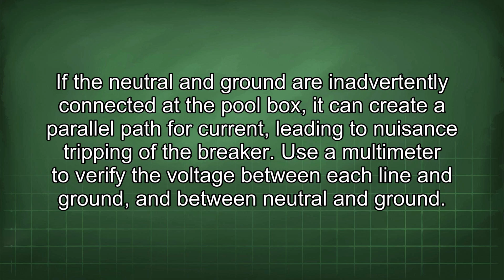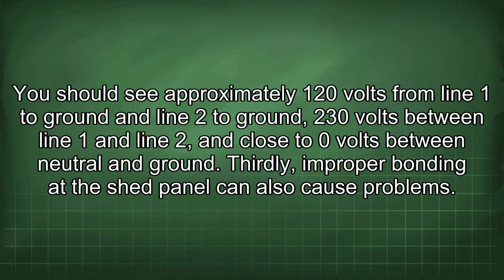Use a multimeter to verify the voltage between each line and ground, and between neutral and ground. You should see approximately 120 volts from line 1 to ground and line 2 to ground, 230 volts between line 1 and line 2, and close to 0 volts between neutral and ground. Thirdly, improper bonding at the shed panel can also cause problems.